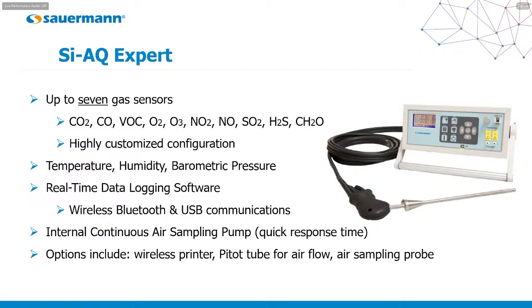Once again, as with the handhelds, you can still measure air temperature, relative humidity, and barometric or atmospheric pressure with the Si-AQ Expert. It has the same data logging software package, and once again can communicate either by Bluetooth wireless communications or a USB cable that comes standard with all the Si-AQ models. It also has the internal air sampling pump that allows for very fast response times from the instrument.